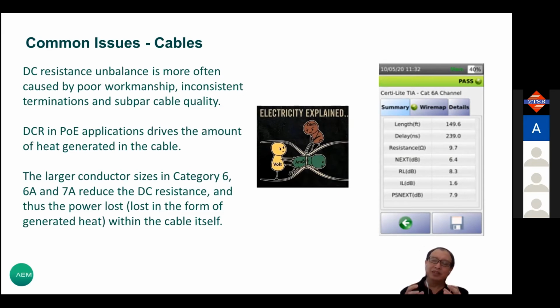The larger the conductor, the lower the DCR value, which allows a lot more current to pass through. But you cannot build a Cat 6A that is 12 gauge or 18 gauge - it does not match with the connector, you cannot punch it in at all because it's too thick. So to facilitate PoE, one of the best cabling systems is Cat 6A because it's much thicker than Cat 5E or Cat 6.